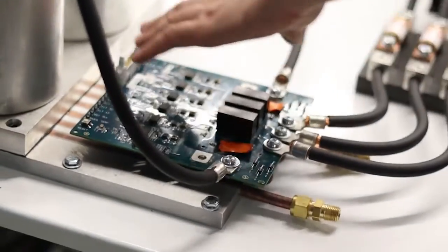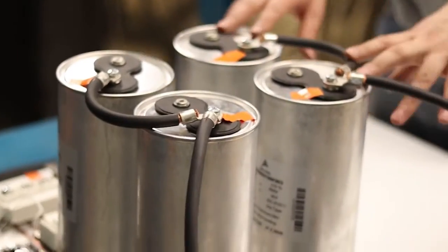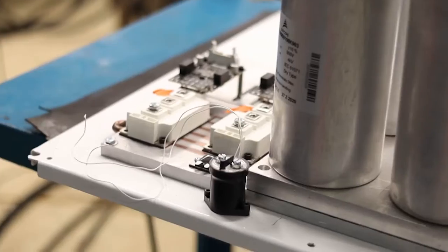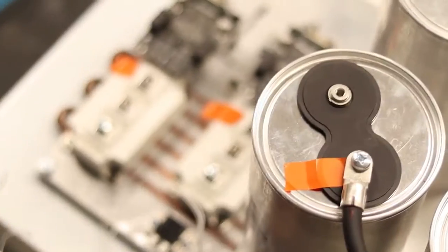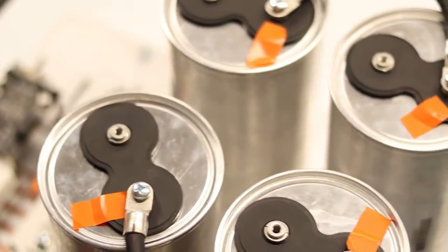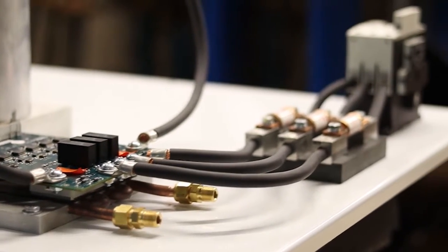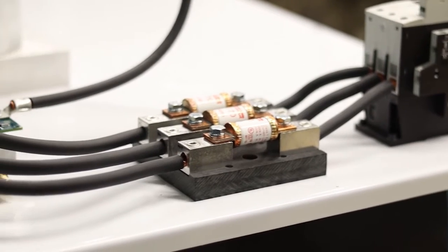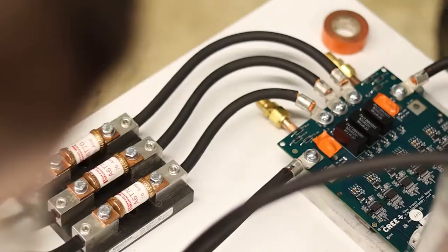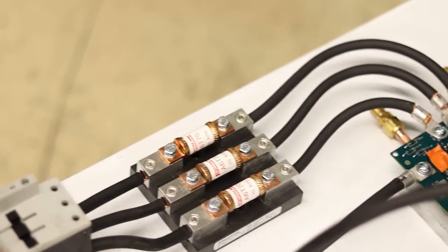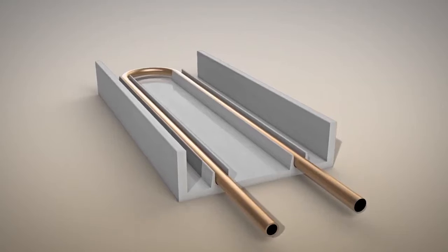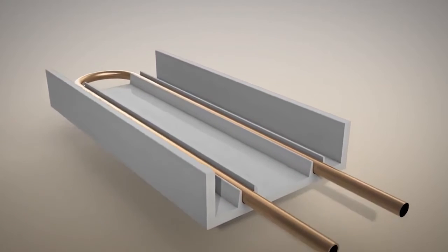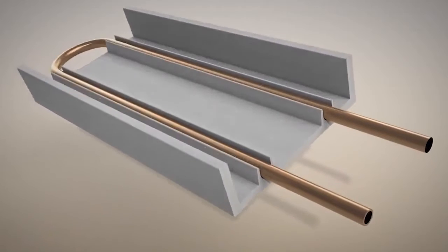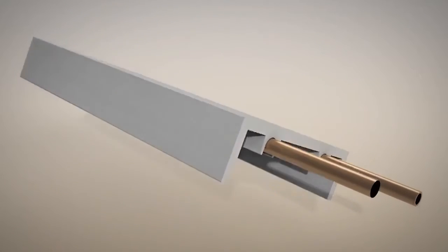After the rectifier, the voltage will be converted into DC voltage, which is smoothed out using a capacitor bank. After the DC capacitor bank, the power travels through the inverter circuit, which takes the newly created DC voltage and inverts it into a single-phase square wave. In a circuit, high current correlates with high temperature. So in order to prolong the lifespan of our project and its components, a water-cooled chill plate is implemented. The chill plate has a copper pipe embedded within the aluminum plate. This pipe is used to carry chilled water through the plate, which will help cool the attached components.